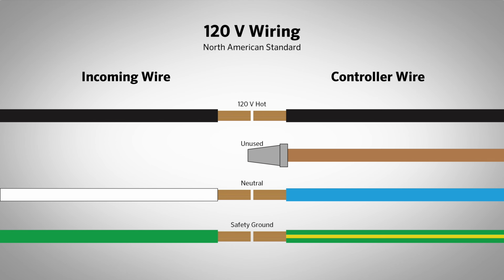The important thing is to connect the right wires. In North America, which is generally 120 volts AC power, this connection is black to black 120 volts hot wires, blue to white neutral wires, and green or green-yellow to green or green-yellow safety ground. The transformer brown wire is not used and should be capped off securely.